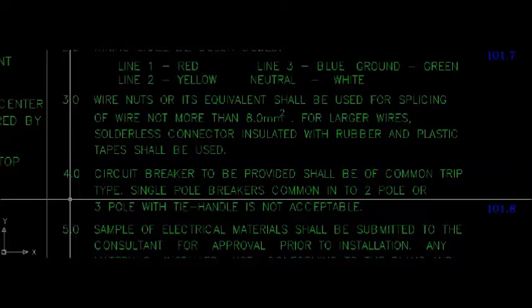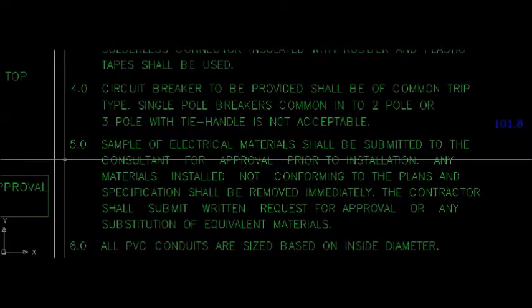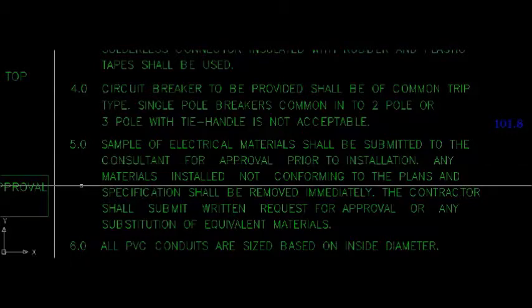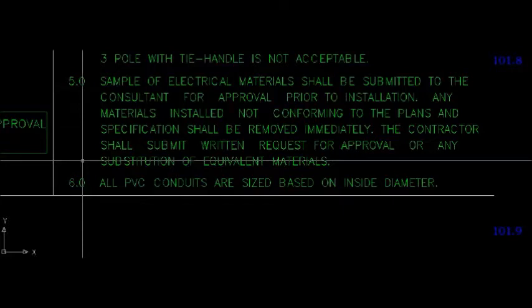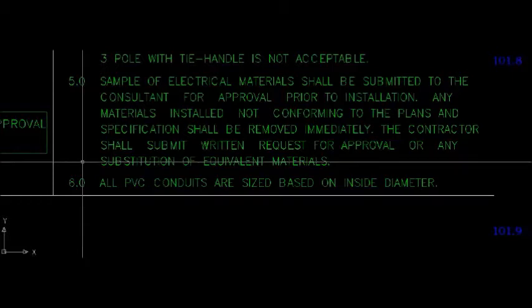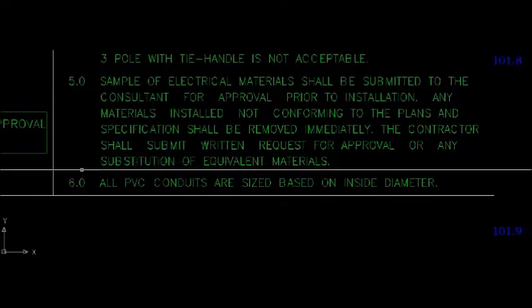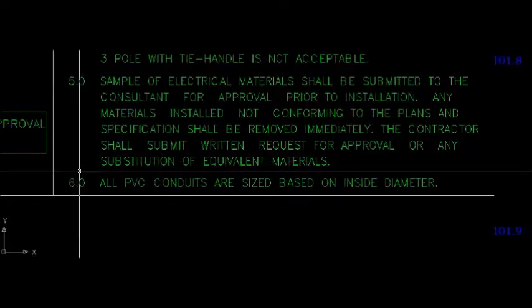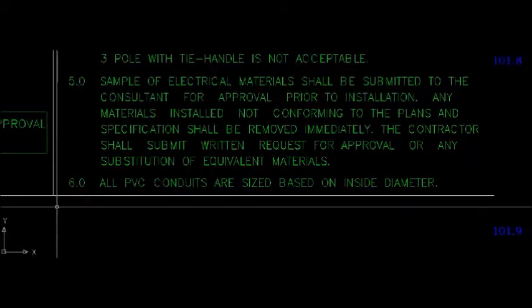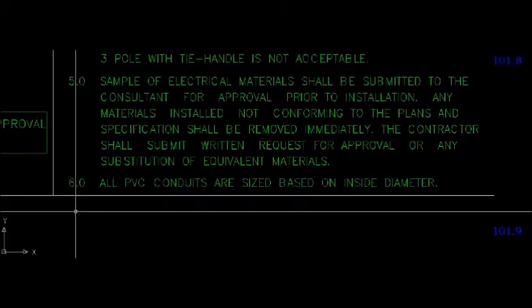Wire nuts or equivalent shall be used for splicing of wire not more than 8 mm squared. For larger wires, solderless connectors insulated with rubber and plastic tapes shall be used. Circuit breaker to be provided shall be of common trip type. Single pole breakers made common in two-pole or three-pole with tie handle is not acceptable. Samples of electrical materials shall be submitted to the consultant for approval prior to installation. Any materials installed not conforming to the plans and specifications shall be removed immediately. The contractor shall submit written requests for approval of any substitution of equivalent materials. All PVC conduits are sized based on inside diameter.